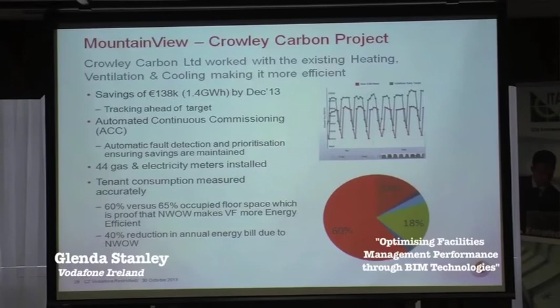Kieran mentioned the automatic continuous commissioning that was put in as part of the project. You get a monthly report that helps you maintain your energy savings. It identifies any faults in the system and prioritizes them based on the money you're losing by not fixing it, so you straight away get things fixed that are costing you money.